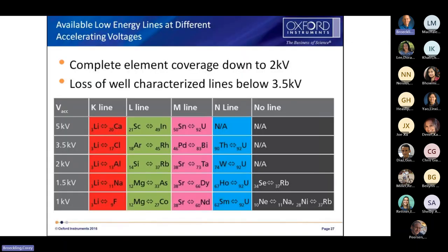Here's what I hope we can do with this - the sub-nanometer resolution in STEM in SEM. This is seven and a half angstrom resolution. That's a TEM-like type image, just goes to seven and a half angstrom. You actually should be able to do the STEM in SEM quite nicely. To push for the low kV, everybody says you have to go to 15 to 20 kV to do EDS. Well, if you look at 2 kV there, that covers the periodic table. So you can actually do the periodic table at 2 kV. The difficulty is the overlap of the lines.